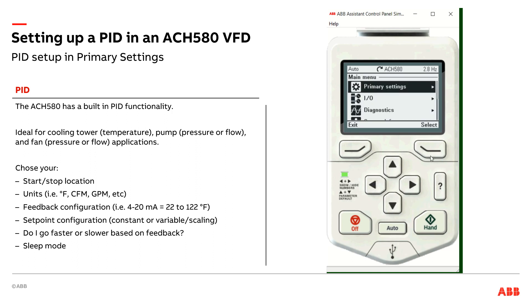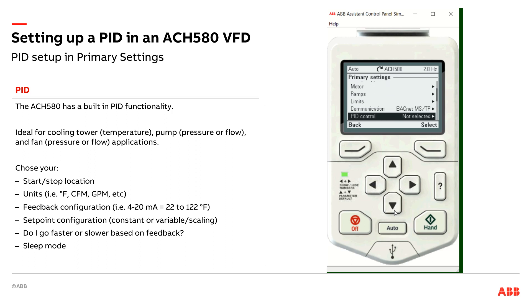First I'm going to go into menu, go into primary settings, and scroll down to PID control and select there. Now I have my first decision: do I want to use the PID assistant where the drive asks me questions, or do I just want to go down the list and answer that information through the list below? I usually do that second option — I find it easier to just go through and select what I need to adjust.